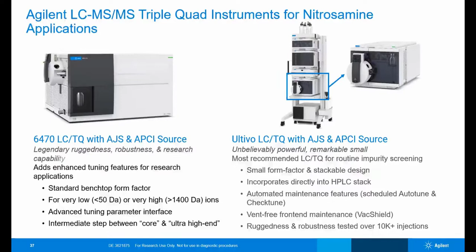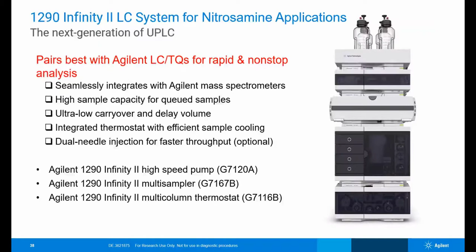1290 Infinity II LC system pairs best with Agilent LC triple quads. It seamlessly integrates with Agilent mass spectrometers. It has high sample capacity for a large number of samples. It is known for ultra low carryover and delay volumes. Integrated thermostat with efficient sample cooling is available, and there is an option for dual needle injection for fast throughput. So this is your HPLC, which we generally couple with MS system.